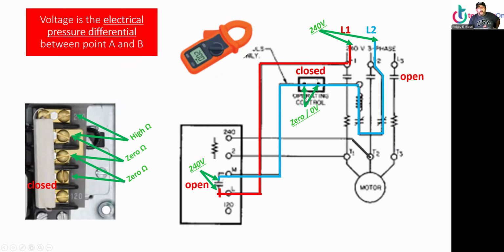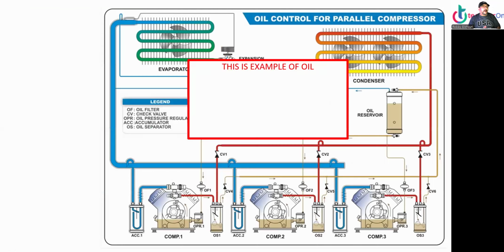But now the control is closed. We're reading 0 volts because we're reading the pressure differential between L2 and L2. Again, voltage is the pressure differential between point 1 and point 2. So if you're reading the same line, it's going to show 0. It's not that there's no voltage. We do have voltage, we just can't measure it. It's very important to understand this, okay? On the left side, with resistance, 0 ohm, 0 ohm, and we have a high ohm reading that shows you it is the heater. Now this is closed, that's why it shows 0 ohm. Maybe this one is confusing. All right, let's move on.